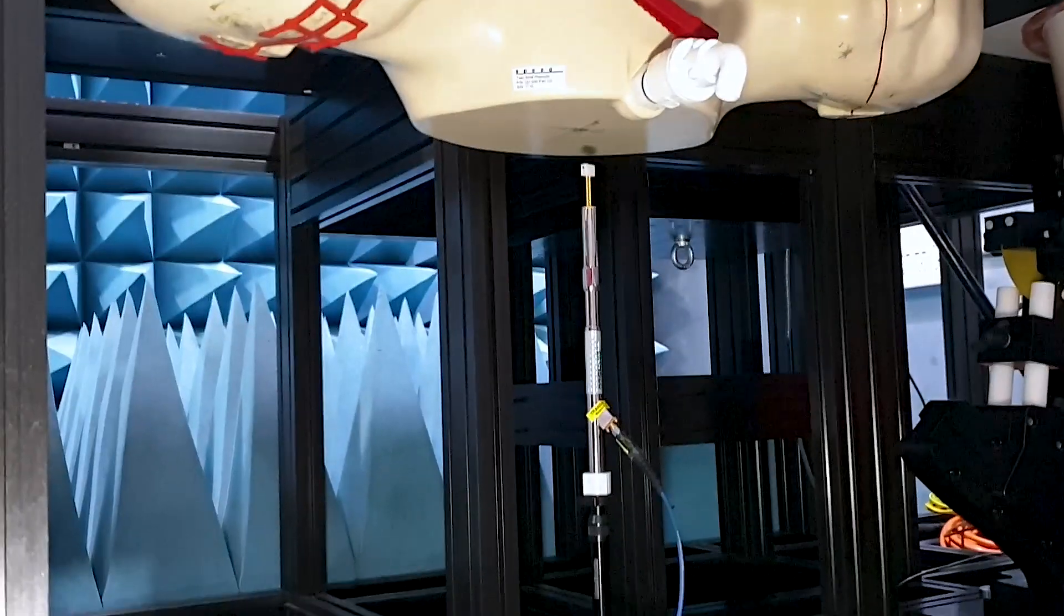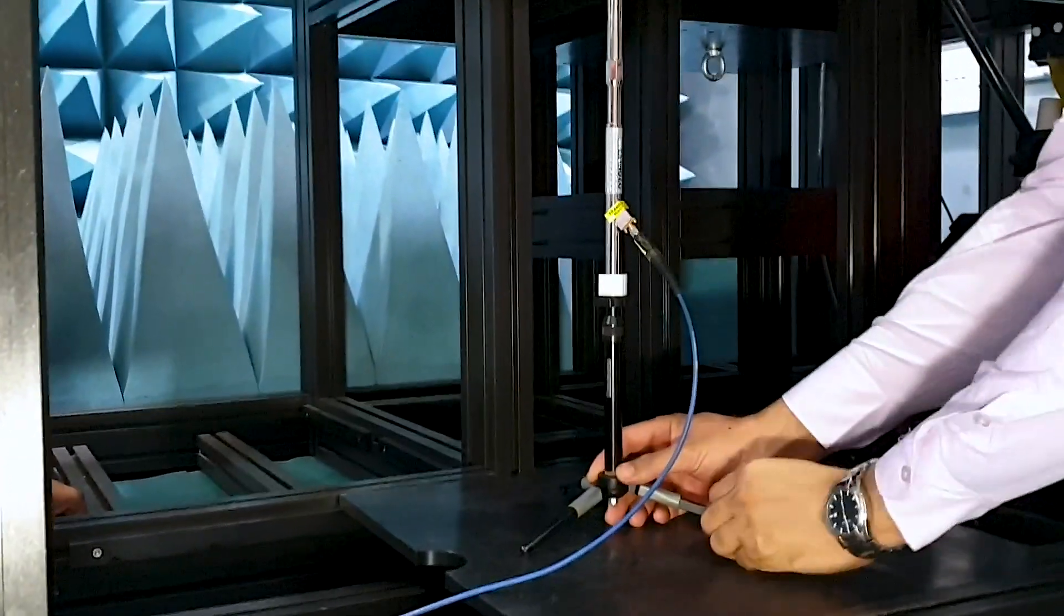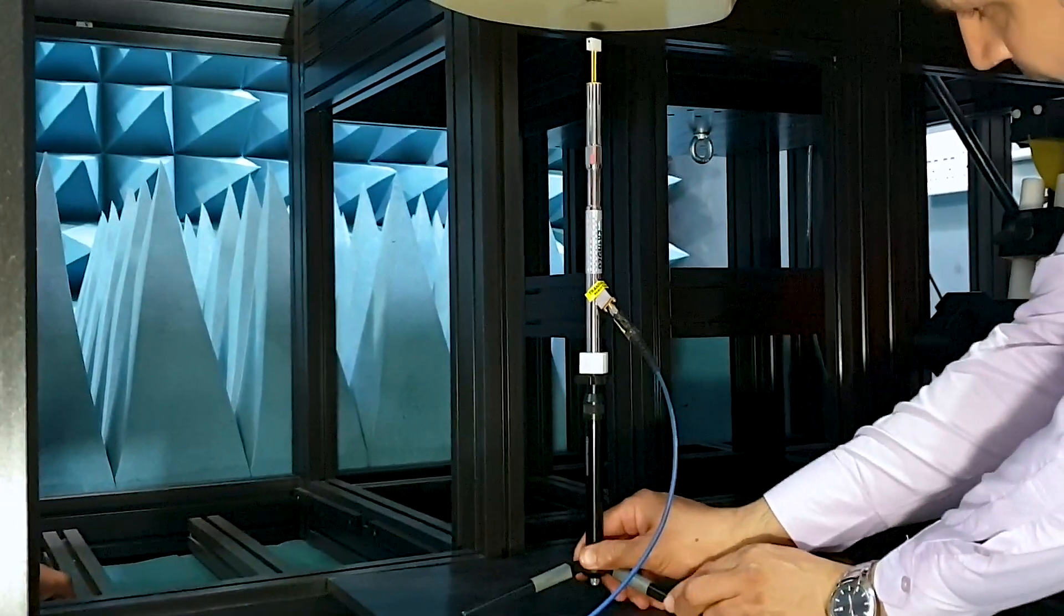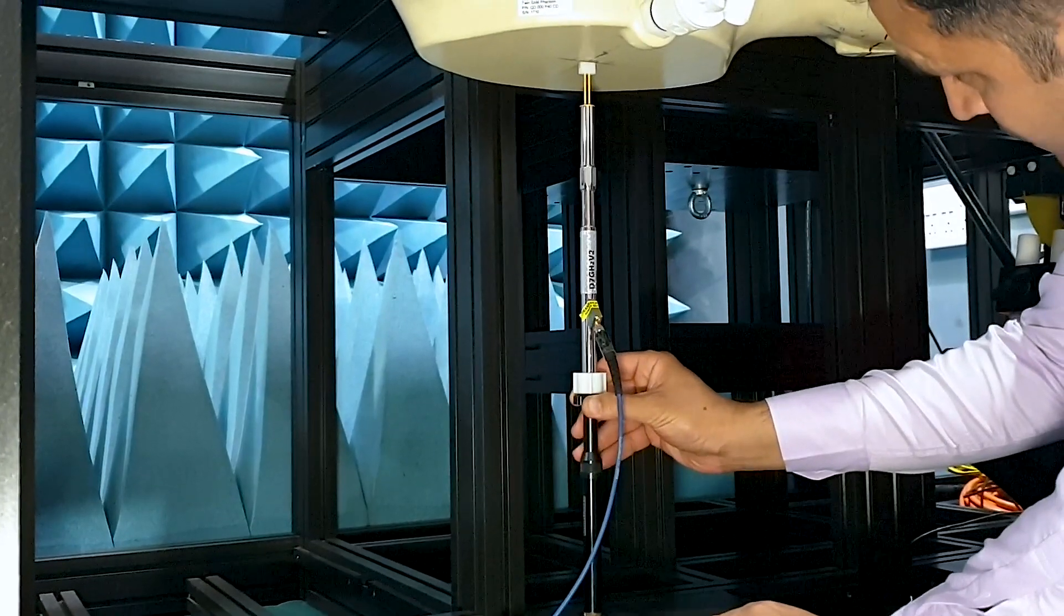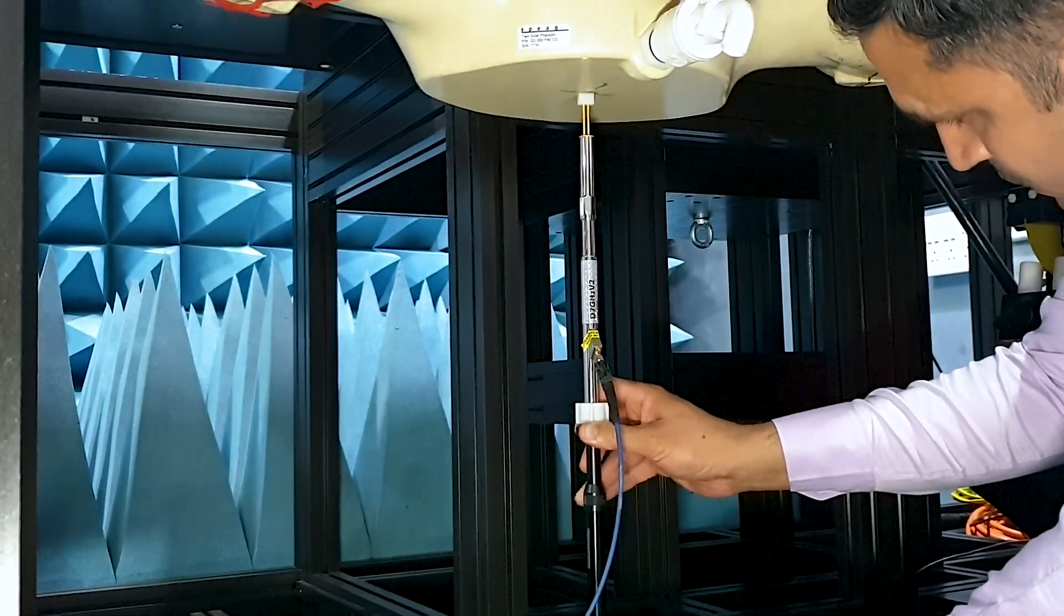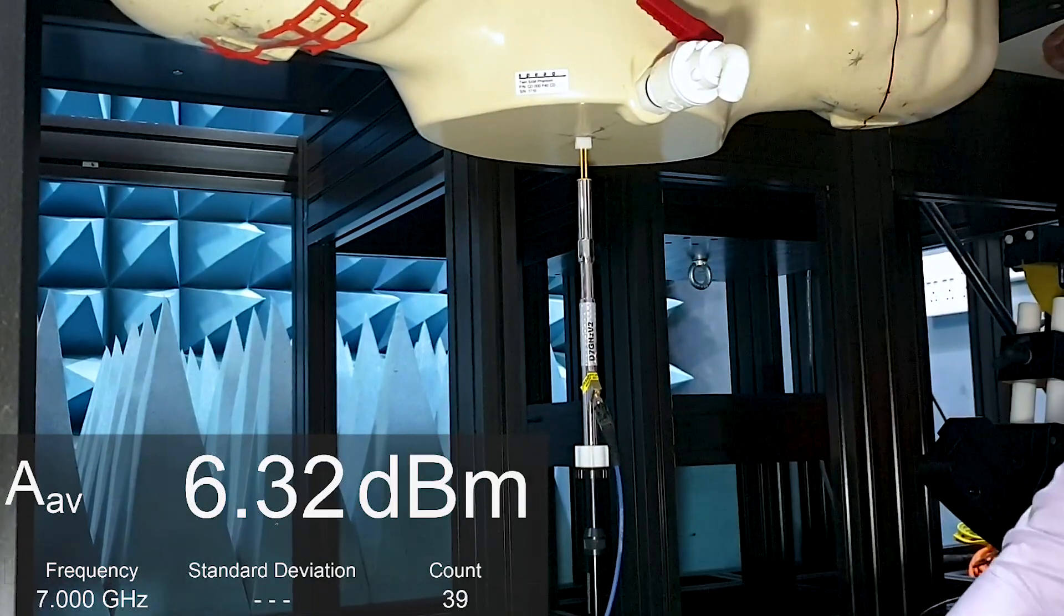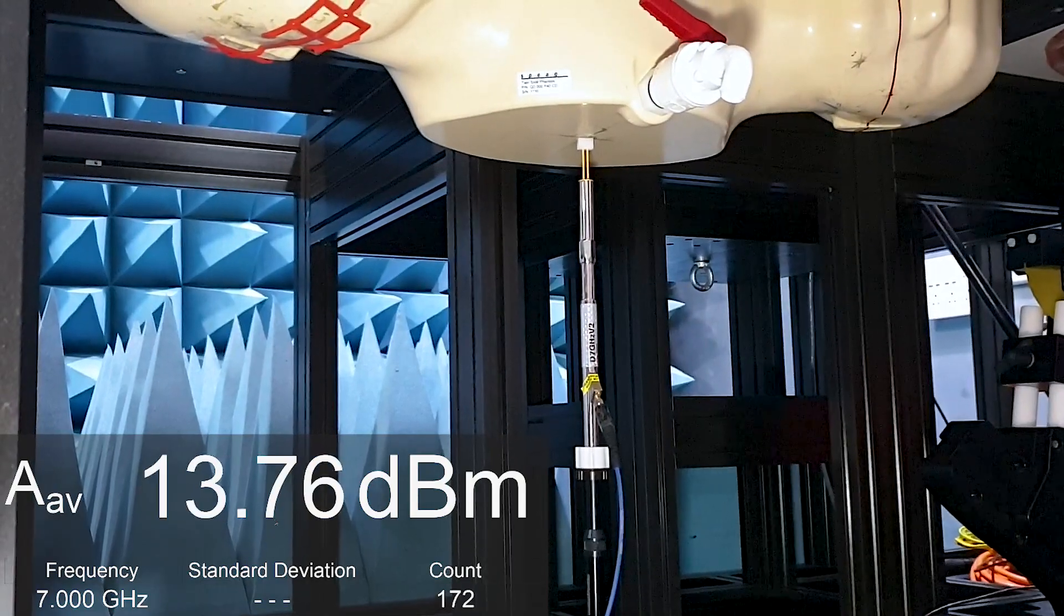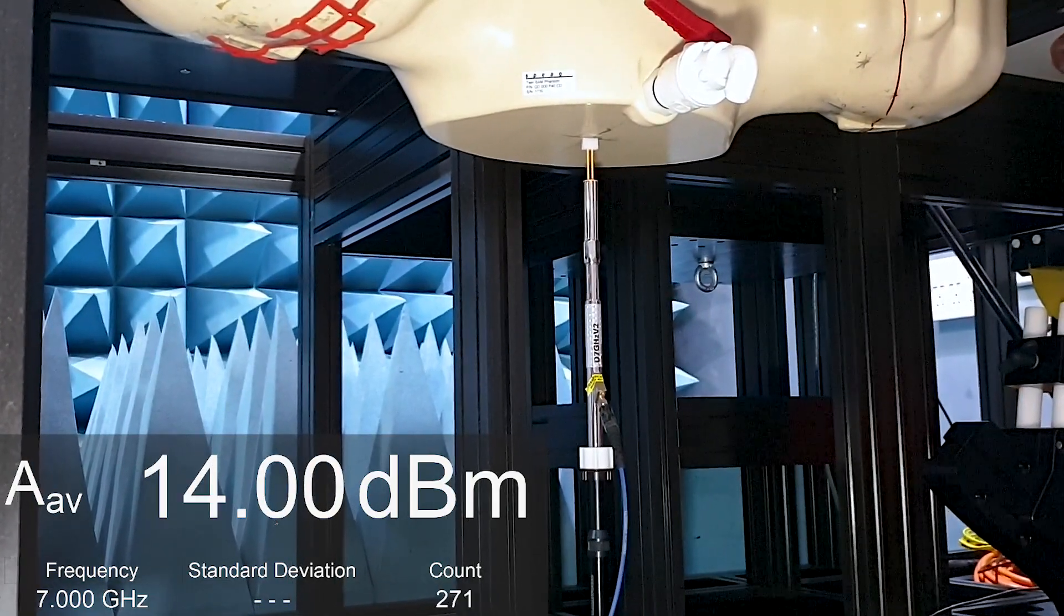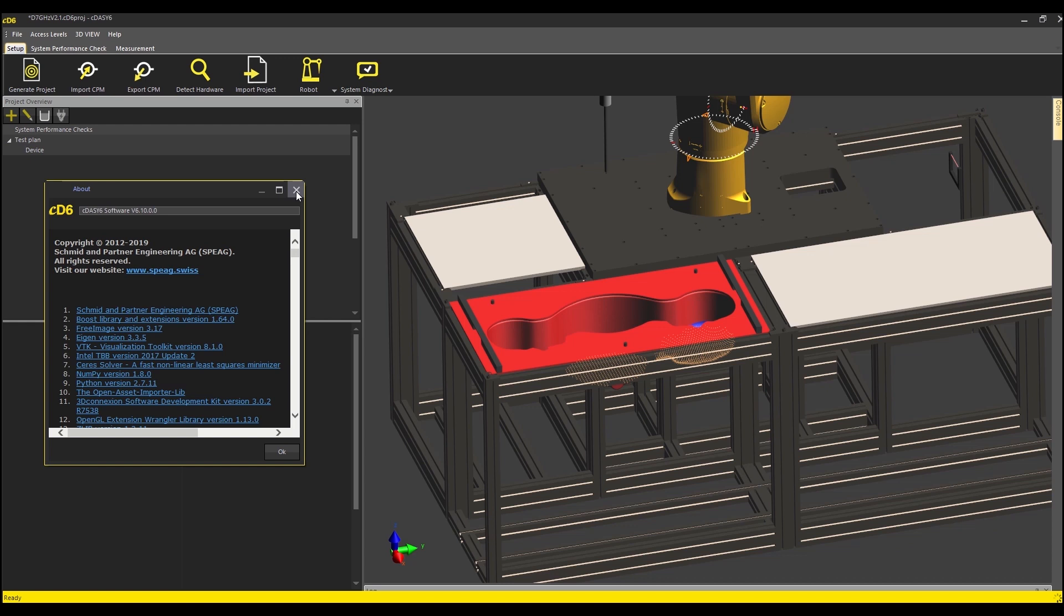To begin, I position the 7 GHz dipole beneath the flat section of the SAM phantom and adjust the signal generator power so that the forward power delivered to the antenna is plus 14 dBm, i.e. 25 mW. We are now ready to set up the measurement in the DASY6 software.